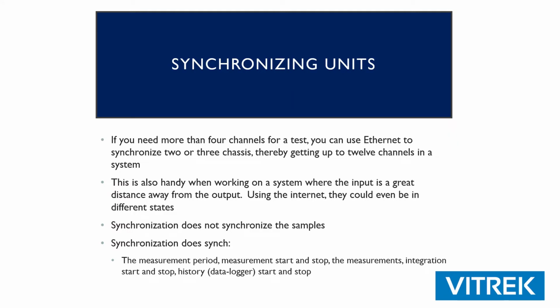Synchronization does not mean synchronizing the samples. They're running as fast as they can all the time, too fast to synchronize with Ethernet, but the measurements are synchronized. That's what counts. So when we synchronize, we synchronize the measurement period, the measurement start and stop, the measurements themselves, the integration start and stop, the history start and stop, and also the configuration.